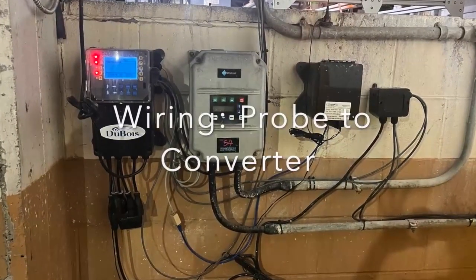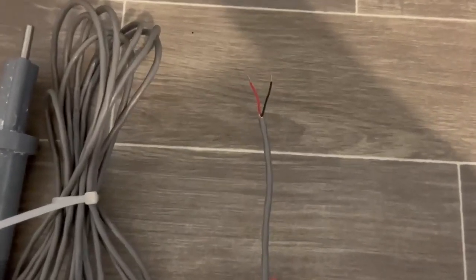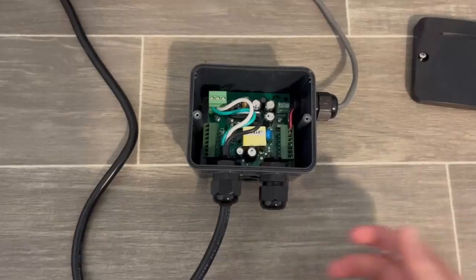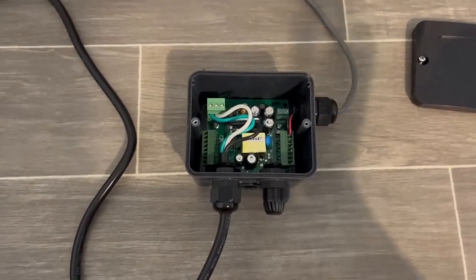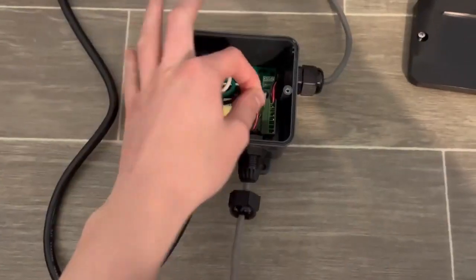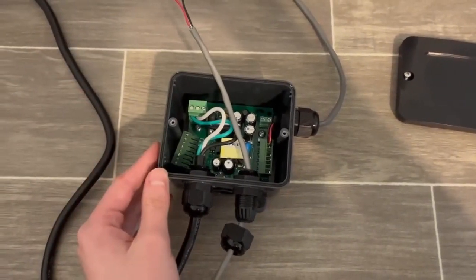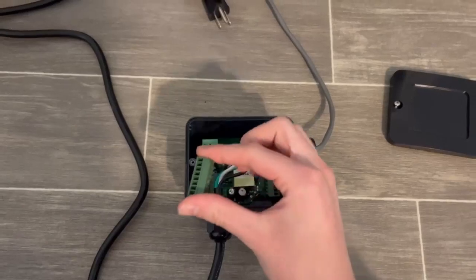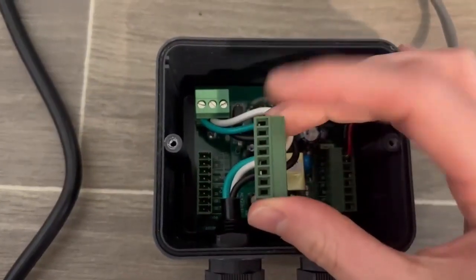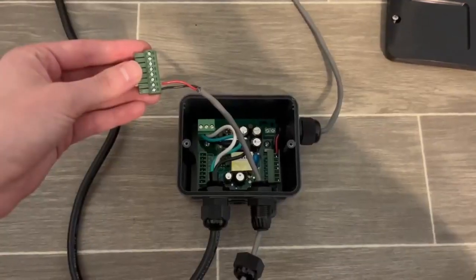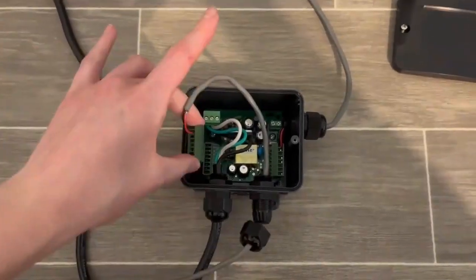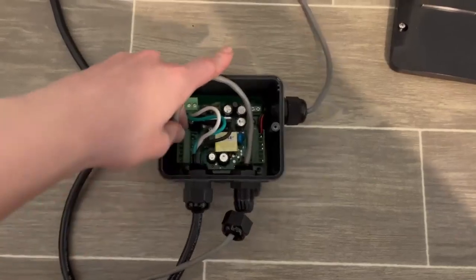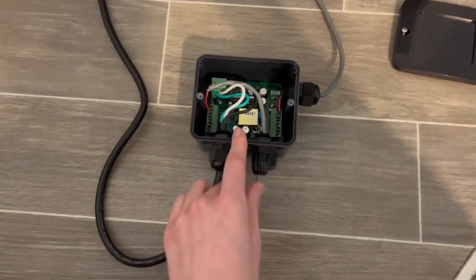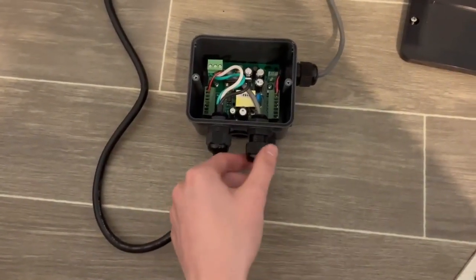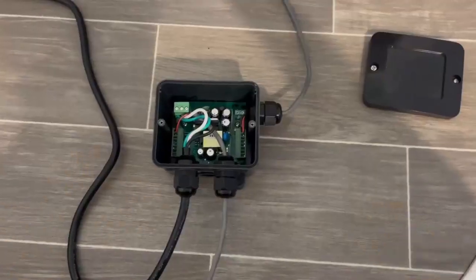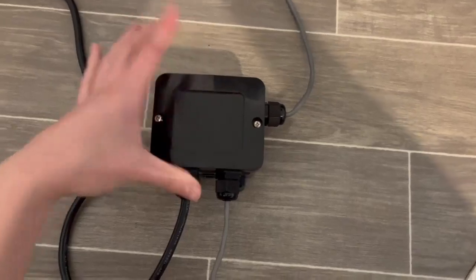Wiring, probe to converter. After attaching your probe to the tank, strip the end of the wire that comes with it. Next, unscrew the bottom right black knob on your converter. Slip the end of the wire through the black knob. Pull the end of the wire through the hole where the knob came from. Pull out the wiring box on the left side of the converter. Check to see which boxes match P1, B, and R. Fasten the black wire into B and the red into R. Place the wiring box back into its original place. Pull the wire taut and then take the black knob and screw it back into place. Place the cover plate back onto the converter and secure it with a Phillips head screwdriver.